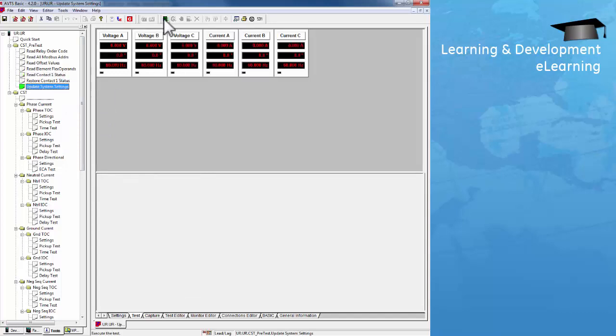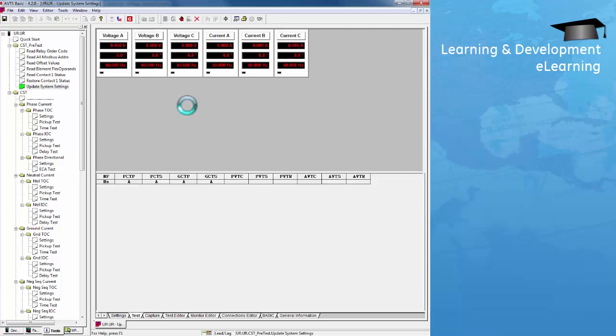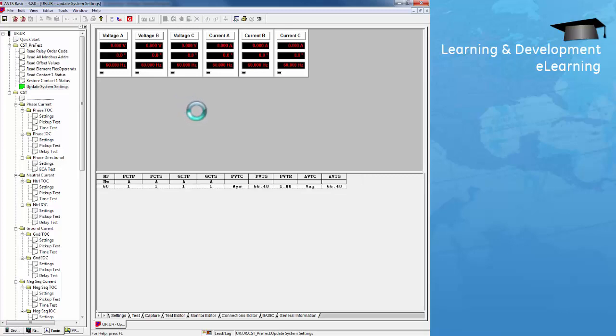Next, I'm going to run update system settings. This test will get the phase primary and secondary CT readings, the ground primary and secondary CT readings, as well as the phase auxiliary VT settings. These settings will be used in the following automation tests.